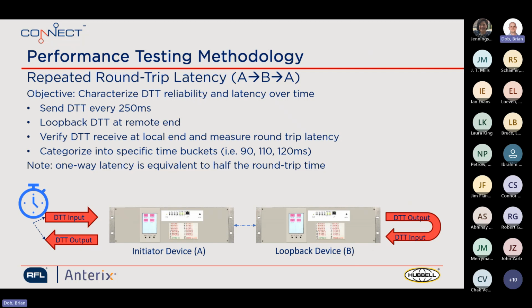So, a little bit about the performance testing methodology we used to evaluate the performance of the private LTE system. We have these GARD 8000s sending the GOOSE traffic between each other over the cellular network. To characterize the performance, we sent a transfer trip signal from the A unit on the left every 250 milliseconds, repeatedly over a period of time, sending thousands of these trip messages. Then at the remote end, we loop back that DTT signal and send it back to the initiator. So it's a round trip type test.